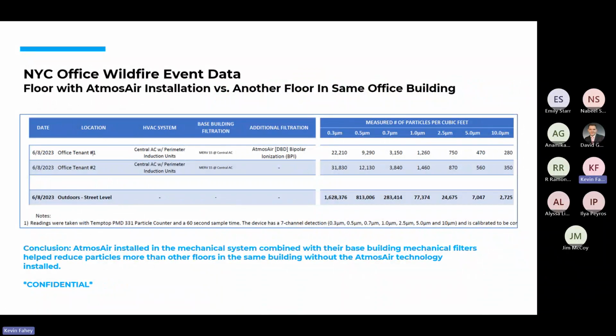This is some data from an engineering firm. It happens to be in Manhattan, a large engineering firm. This was during the June wildfire haze that we had, June 7th and 8th of this past summer. On their floor they have an installation of bipolar ionization, and they're doing monitoring. They also have MERV 15 filters as the base filtration for the building. So they had an industrial hygienist come and sample the outdoor air quality at street level, then take readings for the air quality on a floor with MERV 15 filters but no bipolar ionization, and then in their office with the bipolar ionization.